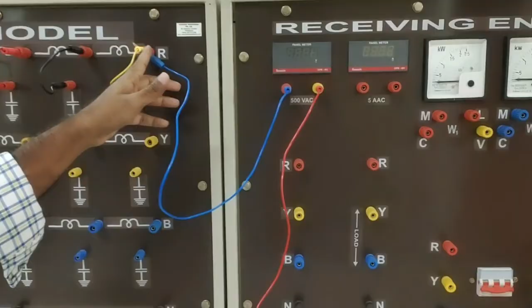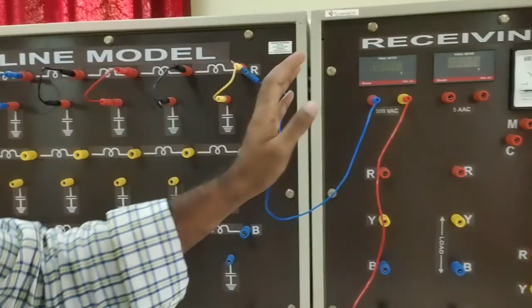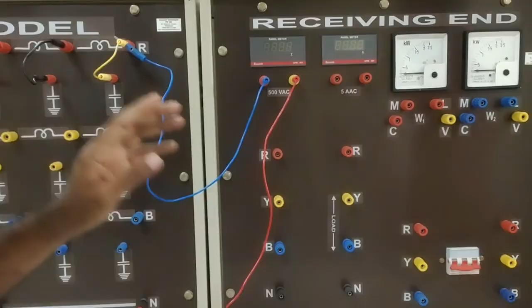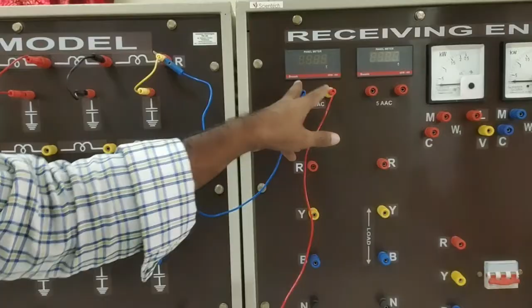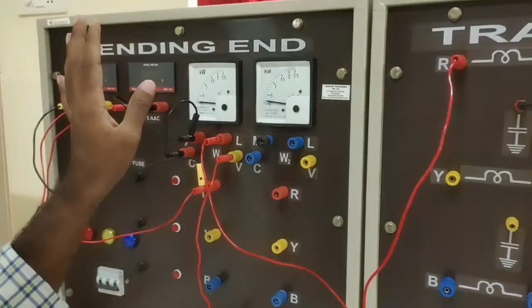After that, at the receiving end, which is the load end, I calculate the open-ended line. The voltmeter's other point is connected to N. So here I take the sending end supply with the receiving end open, then I connect the sending end supply with the receiving end shorted. I apply the rated voltage at the sending end, then take voltmeter readings at both receiving and sending ends, along with ammeter and wattmeter readings. Now let's start the experiment.